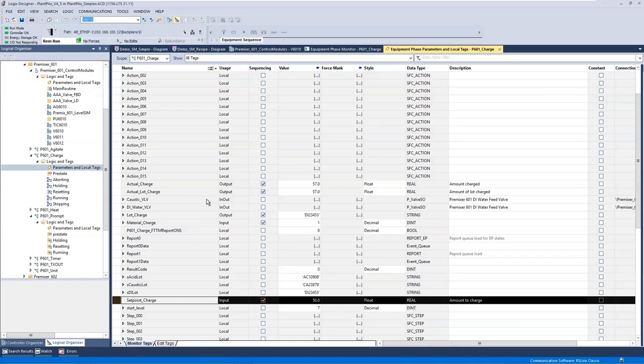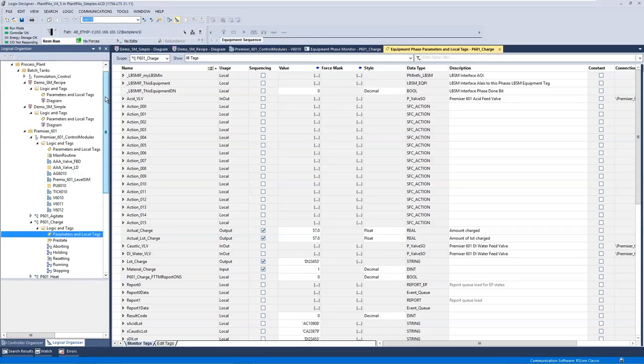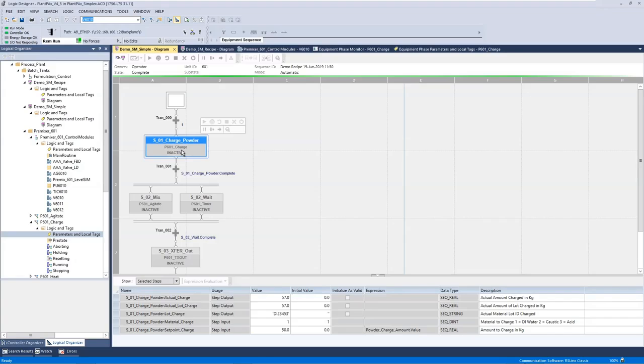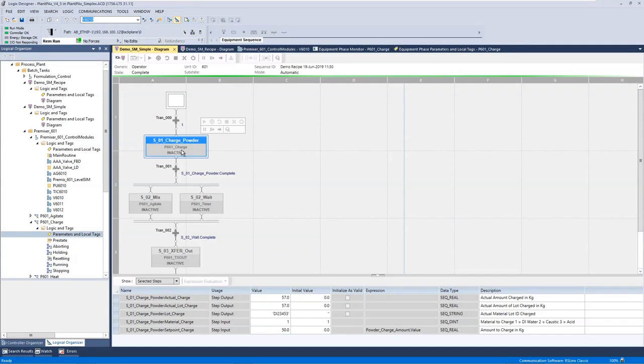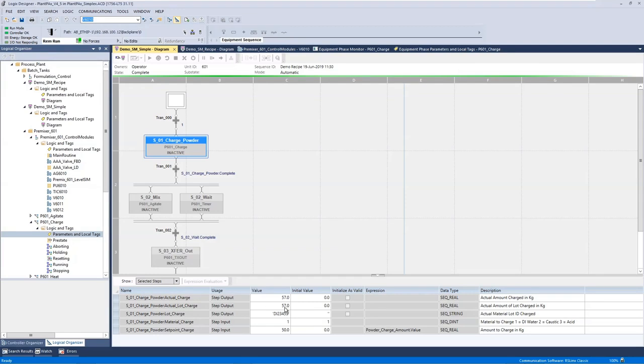By specifying that, then when I use Sequence Manager to control these equipment phases, it will pick up those values and know that those are things that have to be specified in the recipe before that phase starts, and it will look at the outputs, and it will record those outputs if you want to have Sequence Manager execution logging. So here when I select the charge powder, you can see that it knows that the material charge and set point charge are the inputs that have to be specified, and it knows those outputs that are specified are the things to record when it completes.